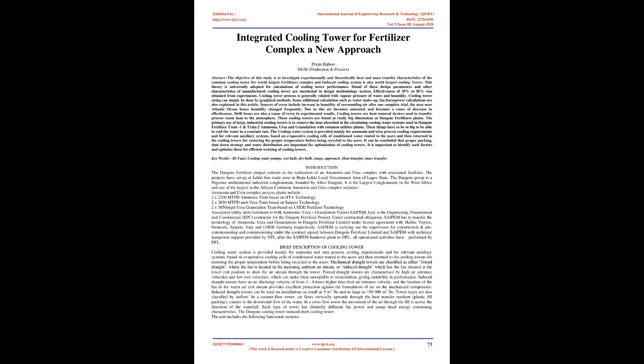The cooling water system is provided mainly for ammonia and urea process cooling requirements and for relevant auxiliary systems, based on evaporative cooling cells of conditioned water routed to the users and then returned to the cooling towers for restoring the proper temperature before being recycled to the users. It can be concluded that proper packing, shutdown strategy and water distribution are important for optimization of cooling towers. It is important to identify such factors and optimize these for efficient working of cooling towers. Keywords: ID fans, cooling water pumps, wet bulb, dry bulb, range, approach, heat transfer, mass transfer.